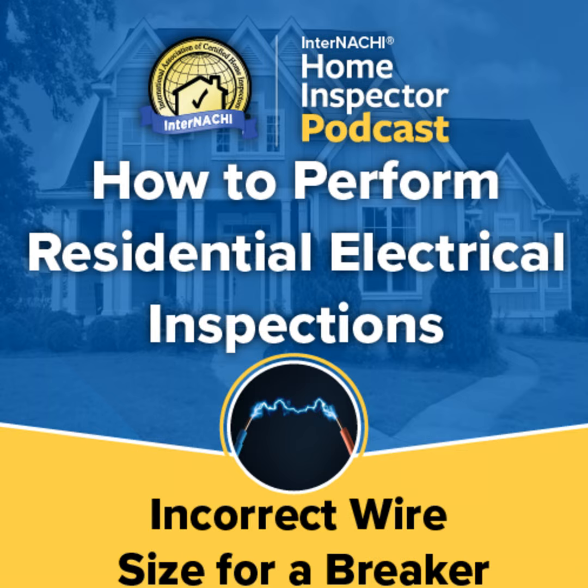This is a defect because of the size of the breaker, 20 amp, it's too big for the size of the wire, 14 gauge. A 14 gauge wire is the minimum size for a 15 amp breaker. The size of the wire connected to the 15 amp breaker is permitted to be bigger. To put it another way, a 15 amp breaker is the biggest size breaker for a 14 gauge wire. They are commonly found to be correctly connected to each other, a 15 amp breaker and a 14 gauge wire.